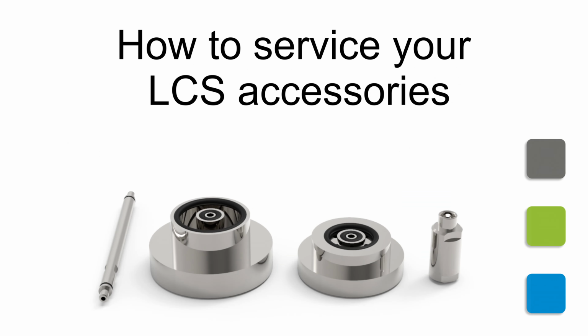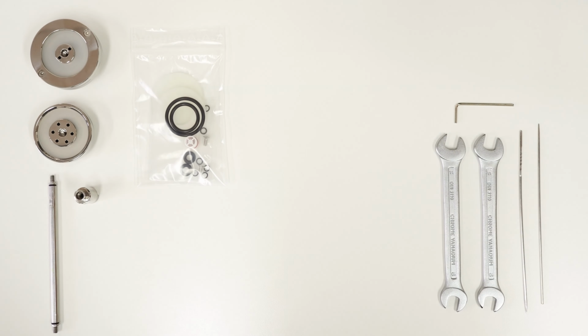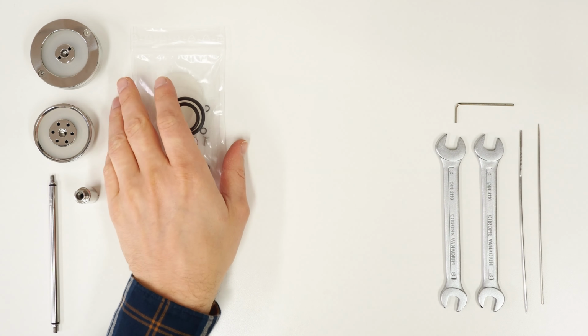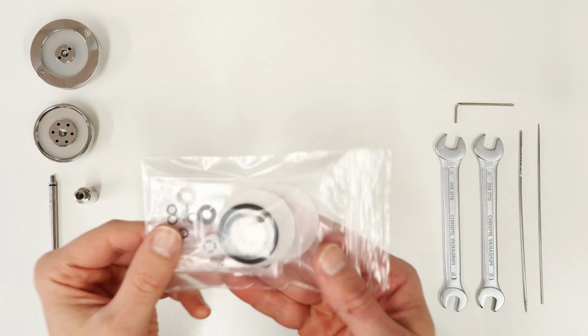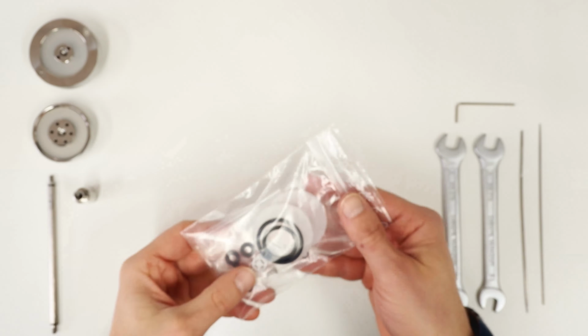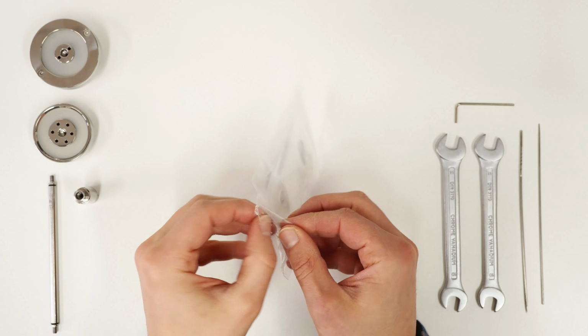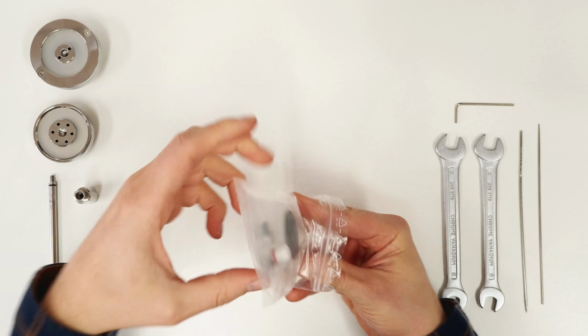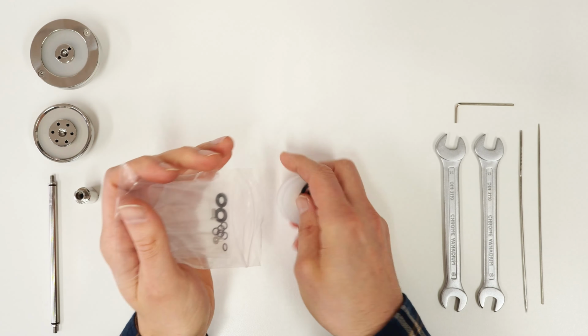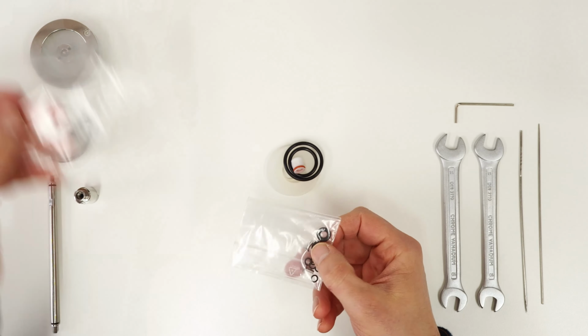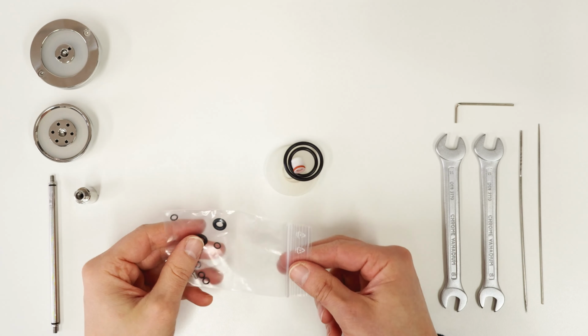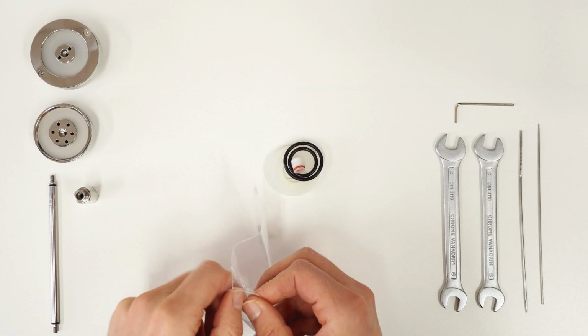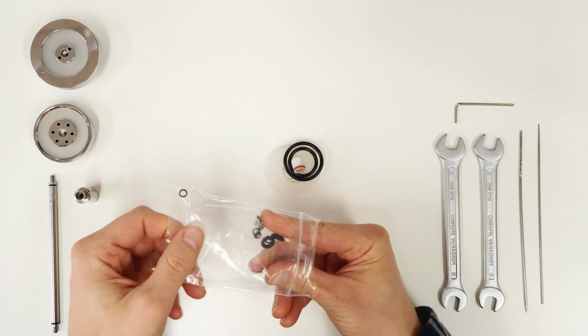In this video, I will show you how to replace the seals on your probe head and cleaning head for the LCS. A few spare seals are included in your accessory kit by default. For more comprehensive maintenance of the cleaning and probe heads, we offer a service kit containing all the necessary seals. If your device is not functioning properly, checking and replacing these seals is a good starting point. The process is simple and can be done by anyone.